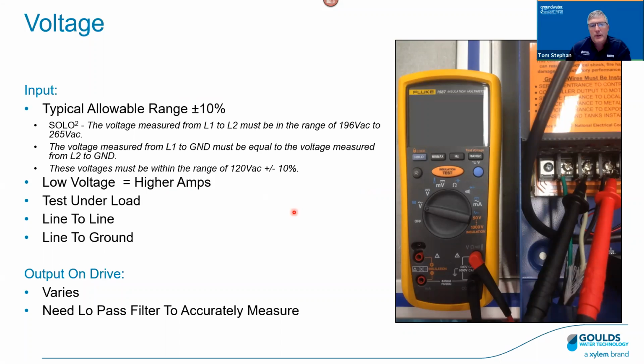Okay, let's talk a little bit about troubleshooting. And we often talk about the VARI or very easy methodology, and that's voltage, amperage, resistance, and insulation. So let's start by talking a little bit about voltage. Normally your voltage tolerance on any piece of equipment is 10% of the nameplate. Well, some drives are actually different. If you look at the Solo 2, that tolerance is a little bit broader than that, and it's 196 to 265. So some VFDs have a little bit more of a tolerance window.